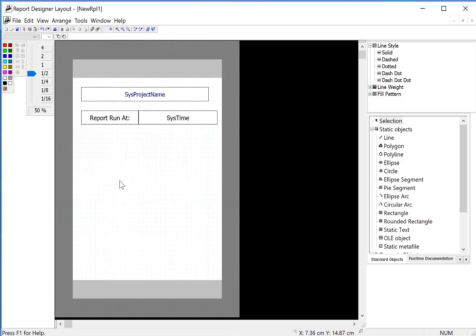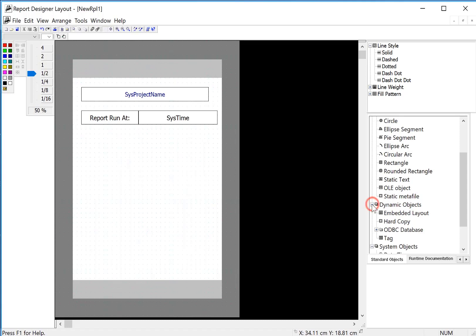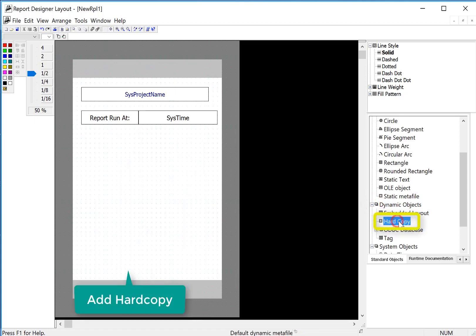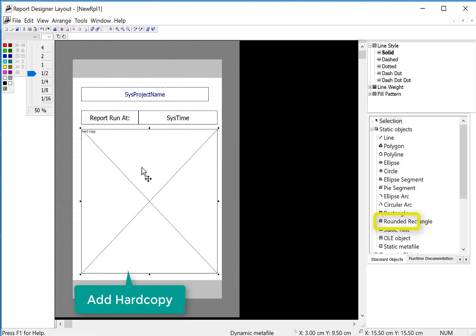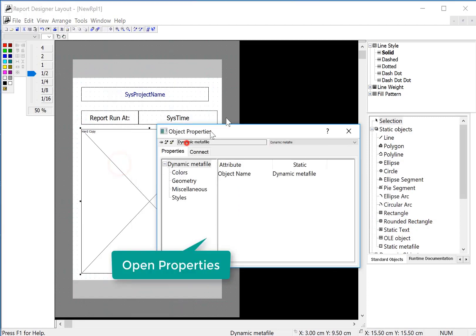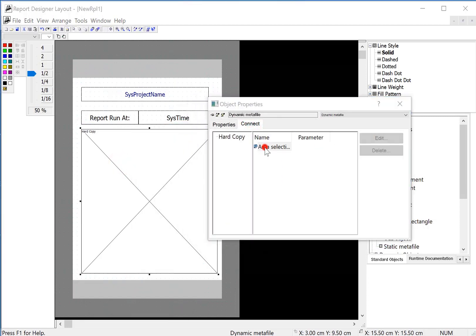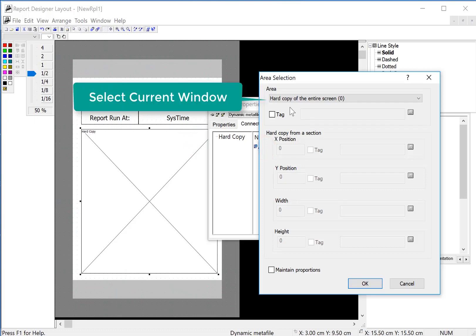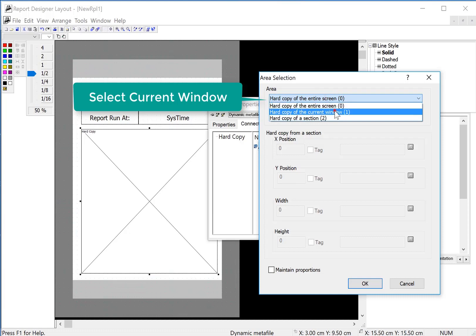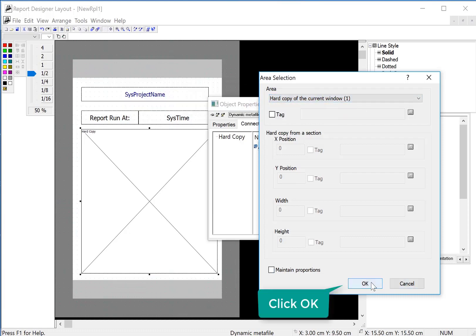For our cover page maybe we want a screenshot of the WinCC Runtime screen. So we'll go under dynamic objects — the hard copy object is what we want to use, but we're going to have to be in the dynamic mode. We'll pull this out and size it, then double click. On connect, the area selection allows me to define what areas of the screen we would like to copy. We can do XY width and height coordinates, or we can just do current window. So I'll do hard copy of the current window and click OK.